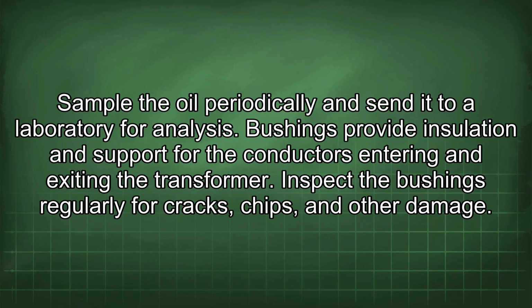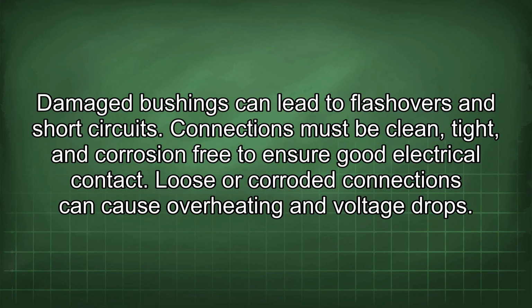Bushings provide insulation and support for the conductors entering and exiting the transformer. Inspect the bushings regularly for cracks, chips, and other damage. Damaged bushings can lead to flashovers and short circuits.